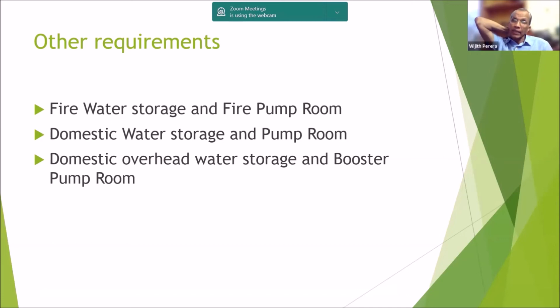Not only that, if it is a sprinkler system, the regulation demands that the fire pumps have positive suction. So it's not only the water storage tank of the fire system that we need to find space for, underground or above ground, whichever the case may be, but for the fire pump room also. So these two need to be very carefully discussed and agreed upon with all parties, particularly with the structural consultant.